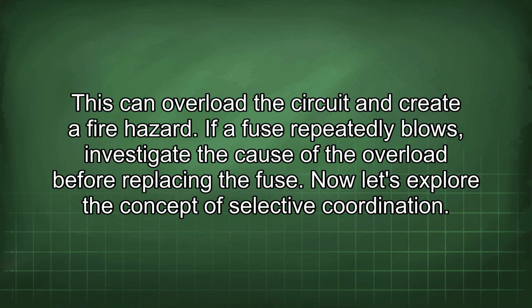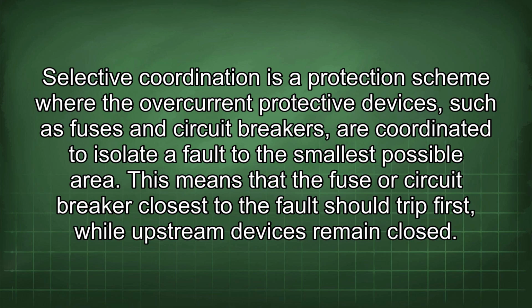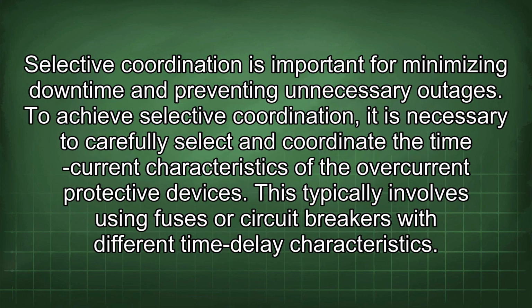Now let's explore the concept of selective coordination. Selective coordination is a protection scheme where the overcurrent protective devices, such as fuses and circuit breakers, are coordinated to isolate a fault to the smallest possible area. This means that the fuse or circuit breaker closest to the fault should trip first, while upstream devices remain closed. Selective coordination is important for minimizing downtime and preventing unnecessary outages.